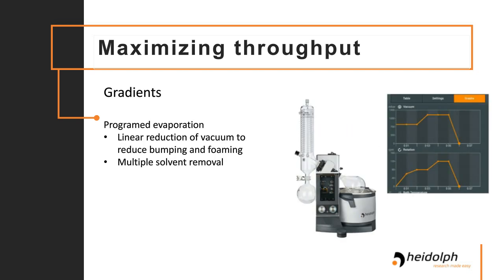Another way to maximize your throughput is with modern rotary evaporators. They will typically have a gradient method for pre-programming your evaporation process. What this does is it lets you set different times and different parameters that will be met at these times, to allow you to pre-program and optimize your evaporation process. What this can also do with single solvent distillations is, if you have a solvent that's prone to bumping or foaming, you can bring down the pressure linearly instead of all at once to gently approach that boiling point, to prevent any increased foaming or bumping from occurring.